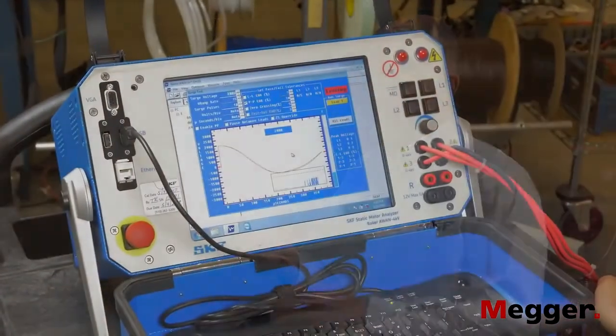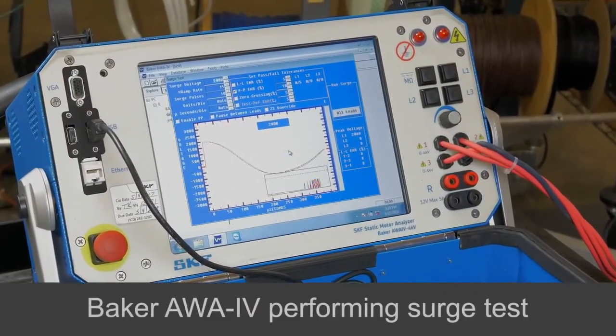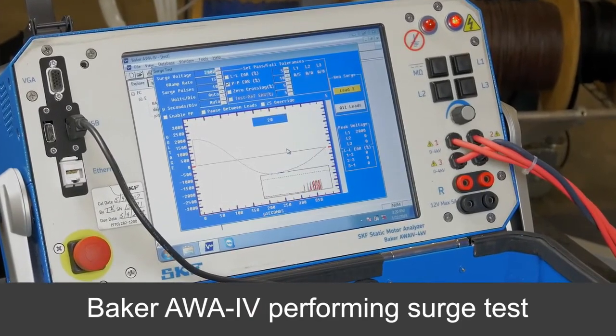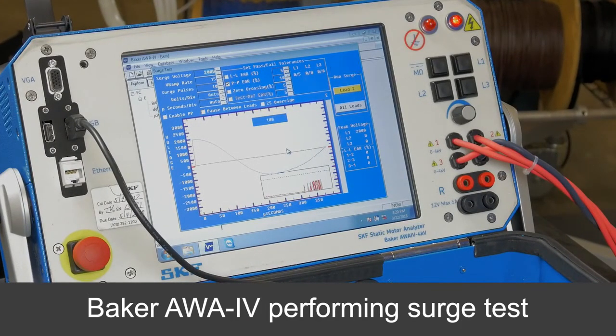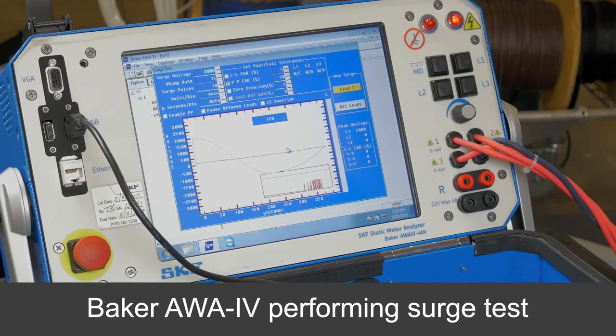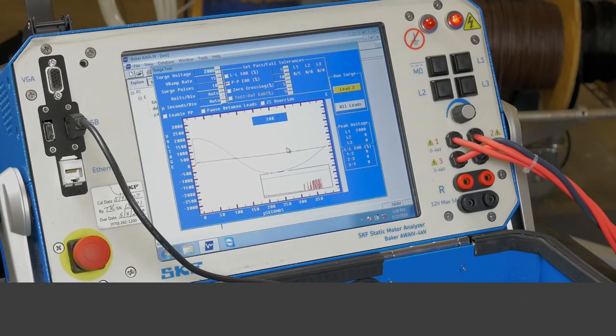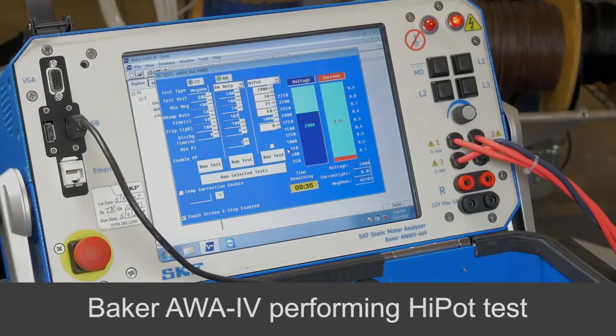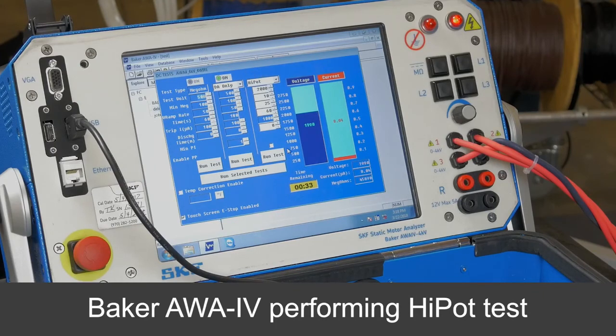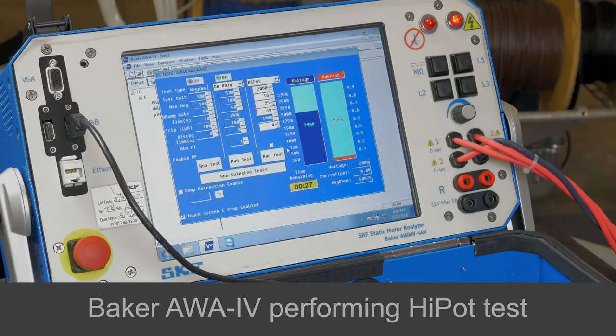So the surge test does put a voltage difference turn to turn, just like the motor really sees in a startup situation, to be able to detect problems in the copper windings. And then the high potential test is another high voltage test that checks your insulation to ground to adequate levels to find problems early enough that it can be a predictive test. And in troubleshooting also, it's very effective. In the one scenario I just gave you, where your motor trips offline, you can find it in a troubleshooting sense very easily.